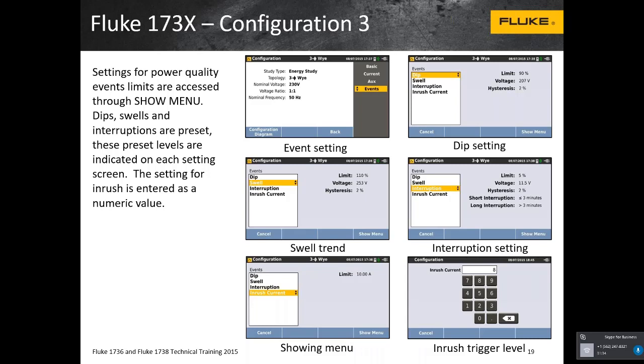Sometimes these problems happen when people aren't working at a facility, or you think something's happening. A common thing we see is a piece of equipment isn't working properly or fails, and you're looking to the company for warranty service. Maybe this is the second time it's failed, and the company comes back saying this isn't their fault—there's something going on with your electrical system, dips, outages, or a voltage problem.